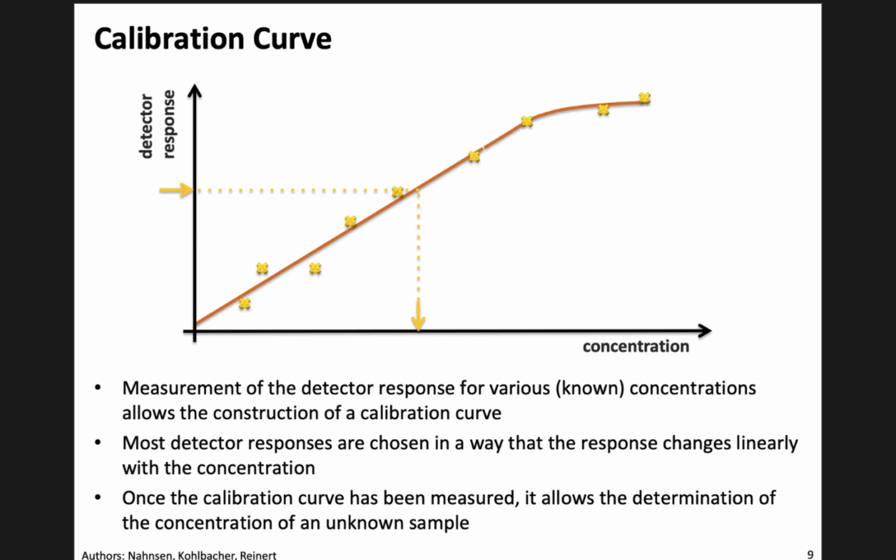Second of all, we tend to have saturation effects in the instrument. The trap has only a limited capacity, and once the trap is full, you can put as much stuff into your ion source as you like. You will not get more ions into this trap, and accordingly, the detector signal will level off at this maximum capacity of the trap. And there are similar issues also when it comes to the detector.